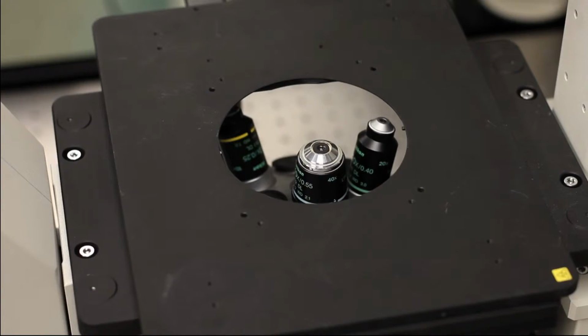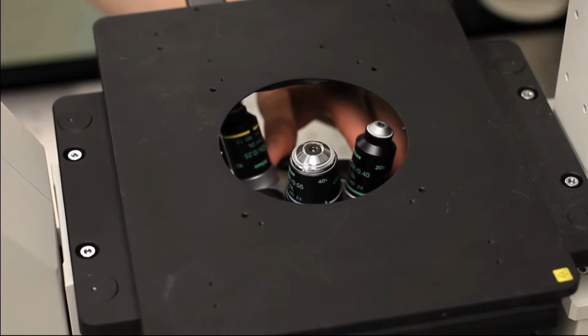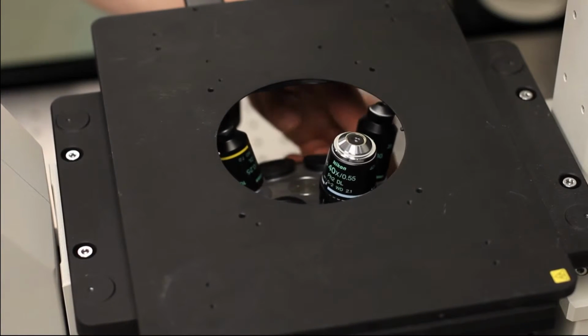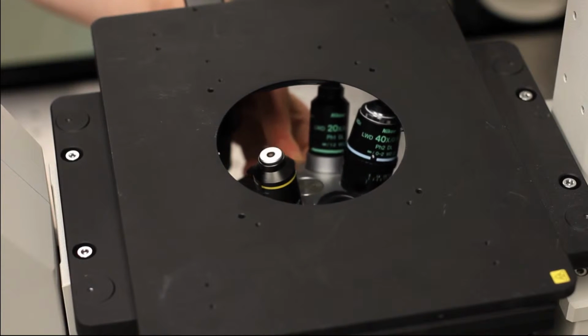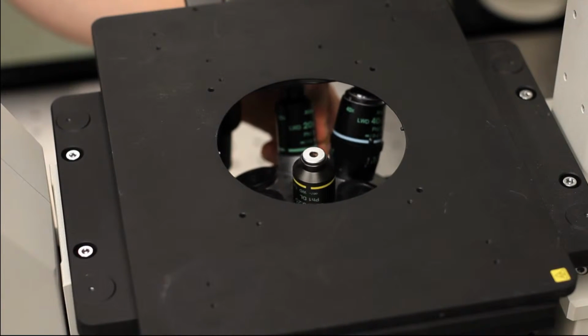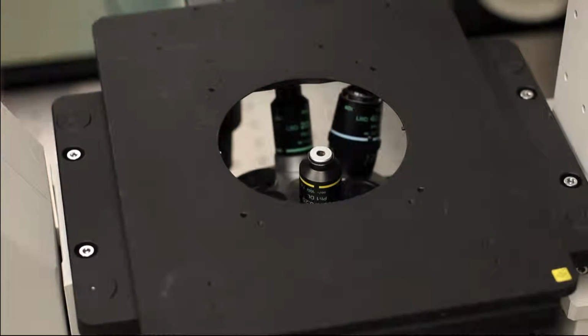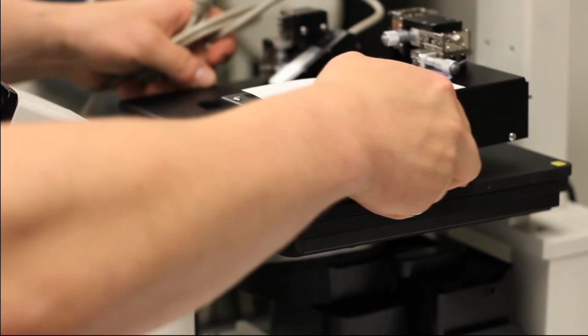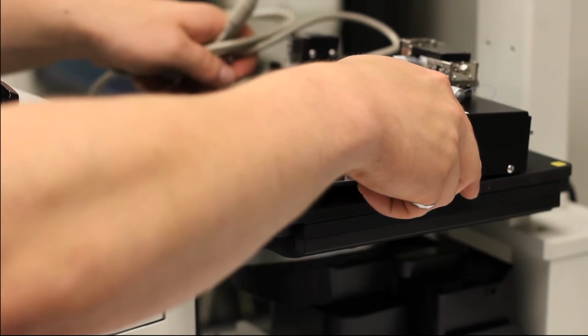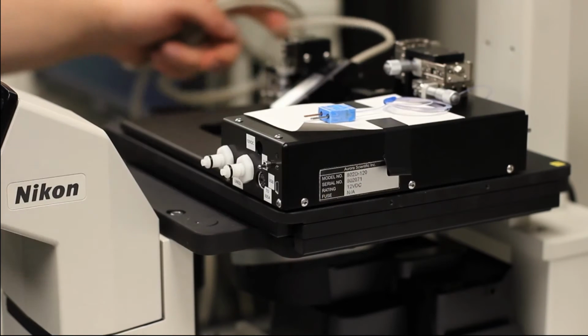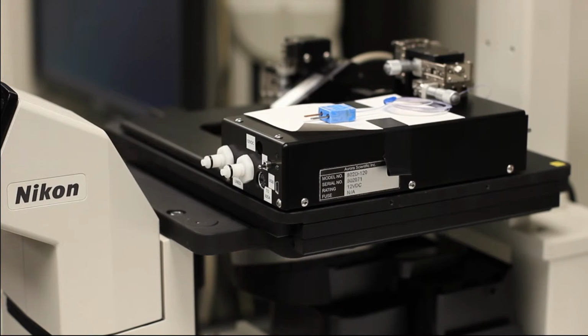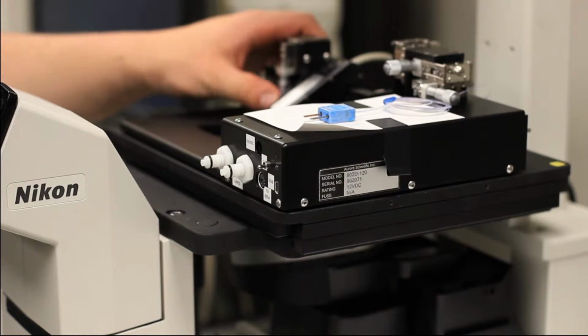With the motor and the transducer mounted, the micromanipulation stages can be used to properly align the motor arm and the transducer tube with the bath itself. The unit is now ready to be placed onto the stage of your inverted microscope. Put the low power objective in place and tilt the condenser head back if possible to avoid bumping any components when placing the 802D onto the microscope.